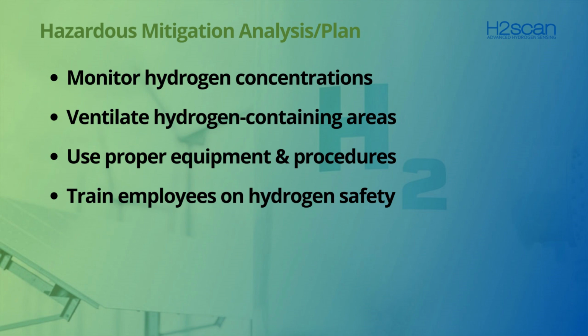We also must use proper equipment and procedures. All equipment and procedures used for handling hydrogen should be designed to minimize risks. And this includes using properly designed and maintained equipment, as well as following the safe operating procedures. And then, of course, we have to provide training to our employees. All employees who work with hydrogen should be trained on safe handling of the hydrogen gas. It should cover topics such as the properties of hydrogen, the hazards of hydrogen, and safe handling of the hydrogen equipment. It should also include how safety equipment works. Based on your configuration of your safety equipment, your employees should know how that safety equipment operates, and they should also be able to recognize when it is not operating properly. They should also know about annunciation from that equipment and how it will annunciate to an alarm center that will allow them to take proper action.